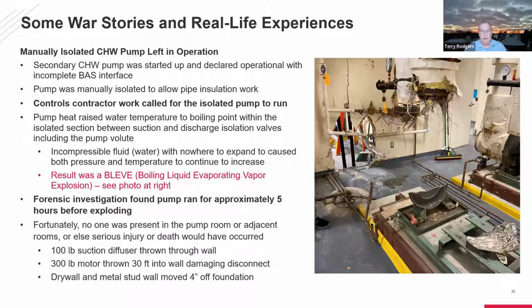And then the steam blast going radially, that wasn't blocked by the diffuser in one direction and the motor in the other, literally blew the walls off the foundation. It was metal stud and drywall, it wasn't concrete or anything, but it literally almost collapsed the room. So in the forensics, we went back and found that the pump had been running for approximately 5 hours before it exploded. So there were a lot of BMS failures. There's some human error in this as well.